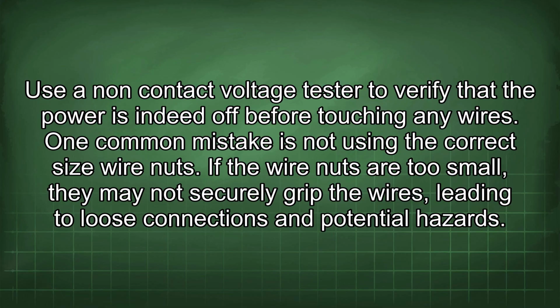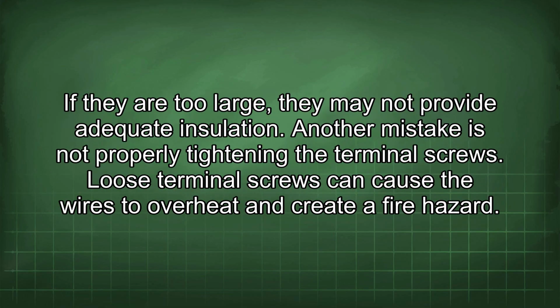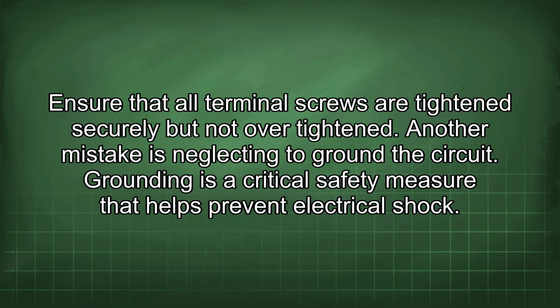One common mistake is not using the correct size wire nuts. If the wire nuts are too small, they may not securely grip the wires, leading to loose connections and potential hazards. If they are too large, they may not provide adequate insulation. Another mistake is not properly tightening the terminal screws. Loose terminal screws can cause the wires to overheat and create a fire hazard. Ensure that all terminal screws are tightened securely but not over-tightened.